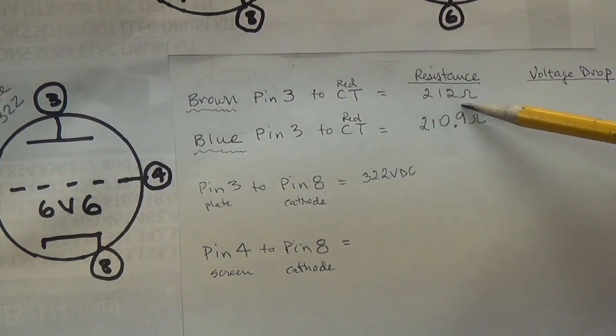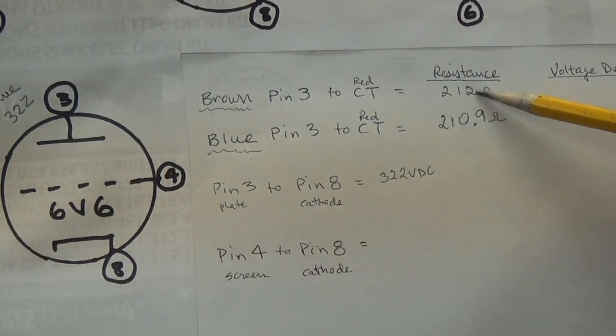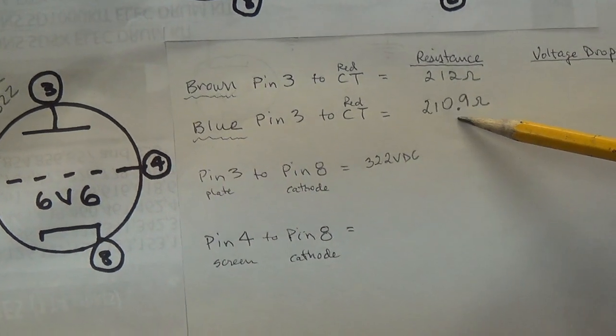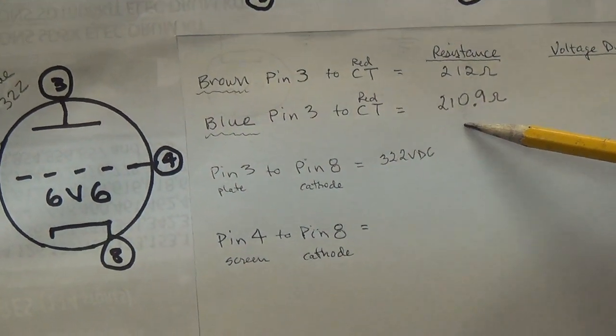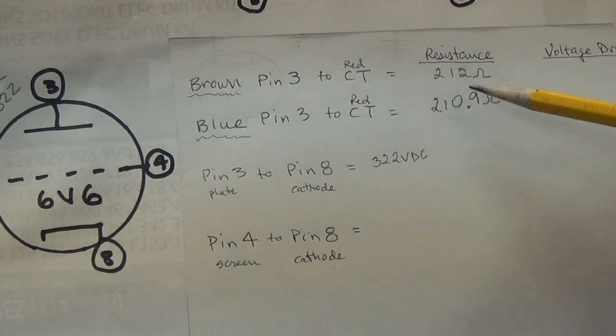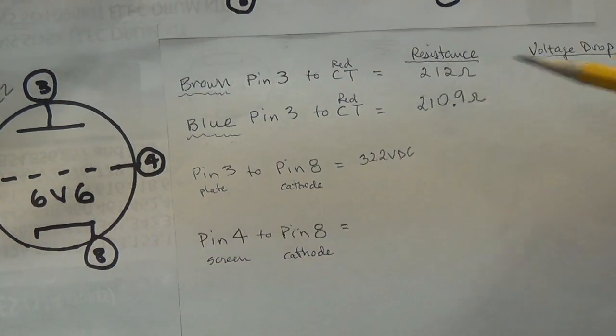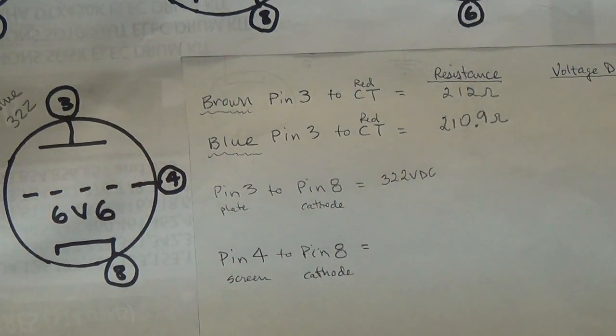A lot of times they'll vary much more than this. If it's really outrageous, like 310 or something, I would figure you've got a bad winding on your output transformer. But this is really close and totally acceptable.